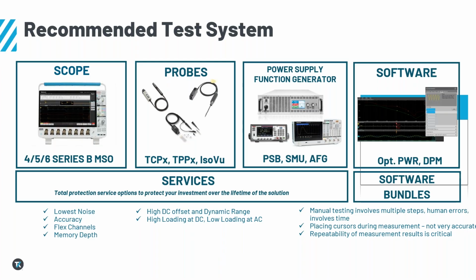So you should have the right probe to capture those signals and make the measurements. Not all probes can have that DC offset, so you should keep that in mind. You should also keep in mind the dynamic range of the probe in order to accurately capture the signal. And you should know the probe loading, which can actually impact the signal you're capturing. So make sure you have the highest loading at DC, and if you're measuring, you should have the lowest loading to accurately see the AC components on the power rails.